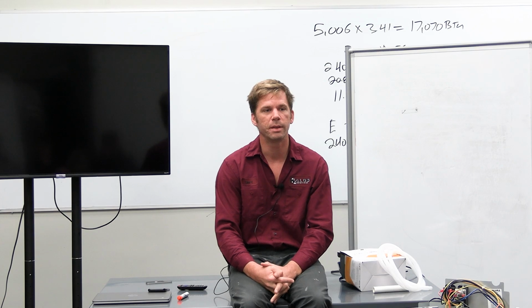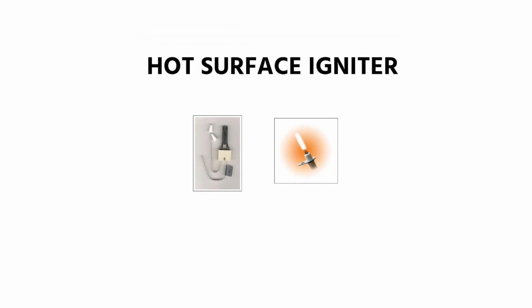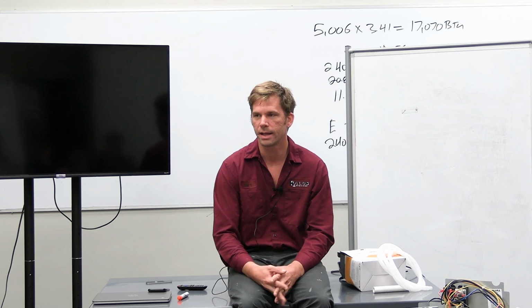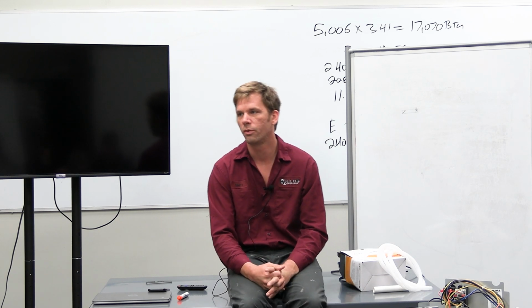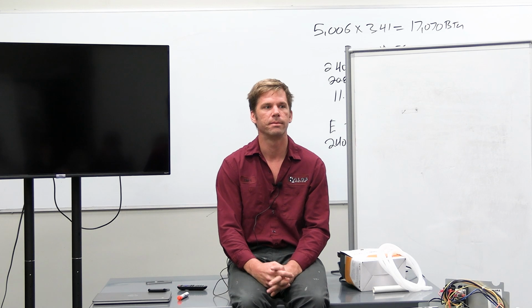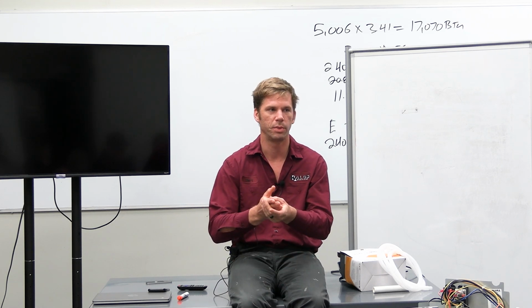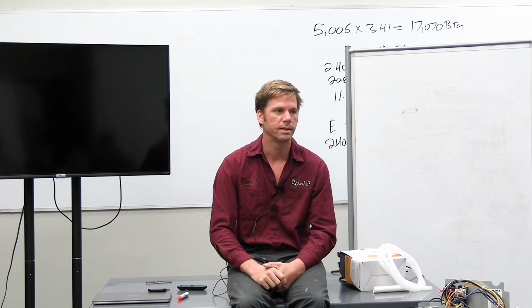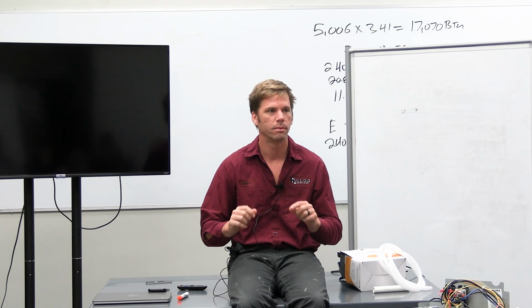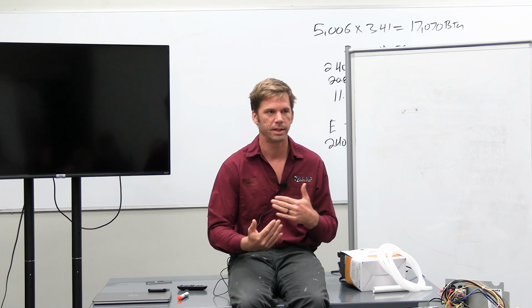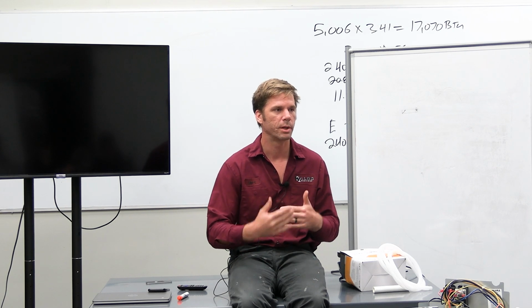So your igniter typically is going to be like a hot surface igniter. You've seen them a lot on furnaces. They just glow bright red, until they get hot enough that they can actually ignite gas. On a pool heater, some of them you will not be able to see. They'll be just tucked away, hidden, completely out of sight, but you can always unscrew that, open that up, pull it out, and inspect it to see if it's got a crack through it or something like that.